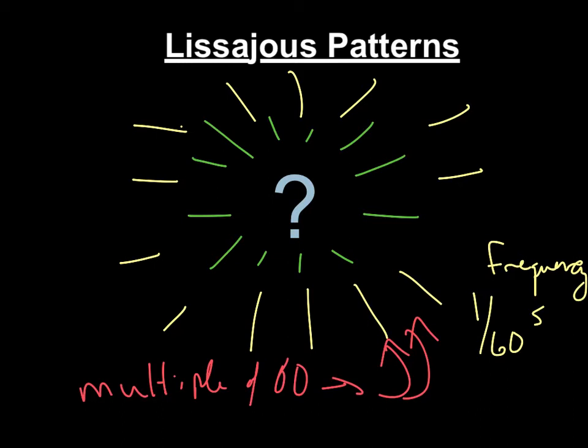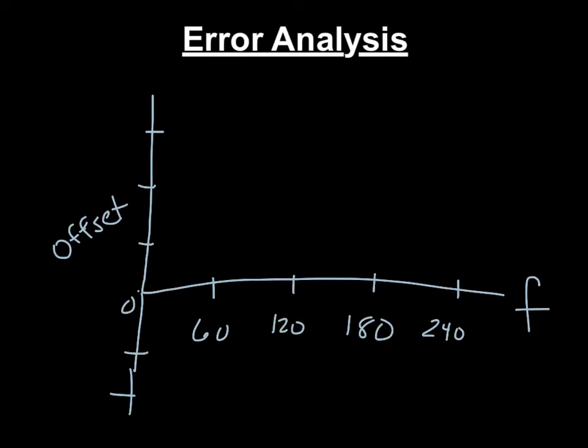Because your function generator, your signal generator, is not calibrated. So if we look at this, we care about the offset. Let's say at 60, you actually measure 54. Well, 54 is 6 below, so this would be, let's say this is minus 3, this is minus 6. And that would be a point right here. Let's say at 120, you measure 121. Okay, well that's plus 1, so let's put that right here. And then at 180, let's say you measure 170. Oh, that's minus 10, that's way down there. And your calibration curve is just going to look like a whole bunch of weird dots.